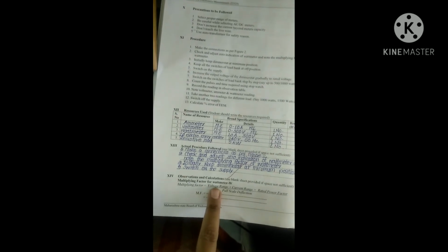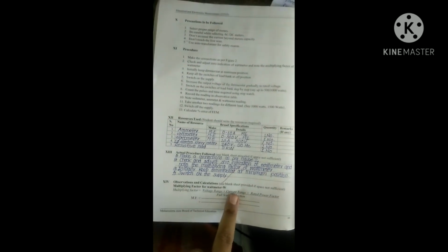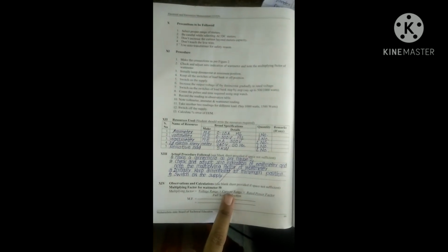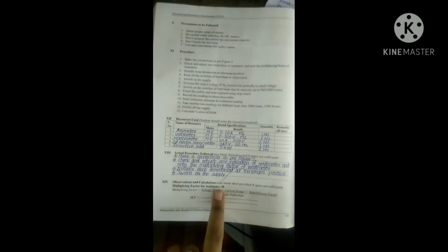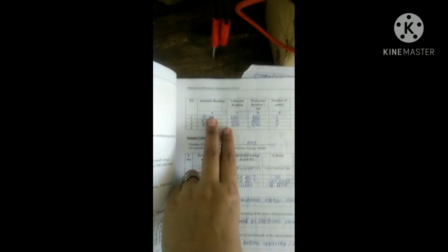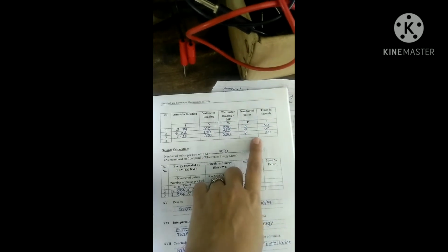So first we have to calculate the multiplying factor. So in this, voltage range is 250 volt, current range is 5 ampere, rated power factor is 1, and full scale deflection is 312.5. So which becomes 4, and this is your observation table for this practical. So first you have to take the reading: ammeter reading, voltmeter reading, wattmeter reading, number of pulses and time in second. So now we will start the practical.